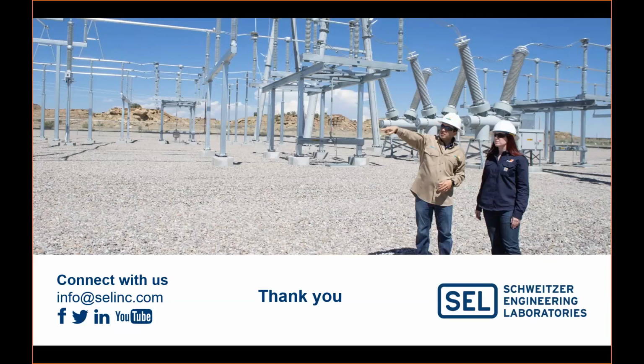All right. Another question is asking, what is the benefit of using ultra-high speed relays if the breaker will need 2 to 3 cycles to operate? Yes, that is an interesting one. Actually, the total fault clearance time is a combination of relay operation time plus breaker operation time. The relay part that used to take maybe 20 milliseconds, we are now claiming to be 2 milliseconds. So we are doing our job much better than before, reducing the time by 10 times. But the problem is on the breaker end. Unfortunately, we cannot control breaker times if you have existing installations.